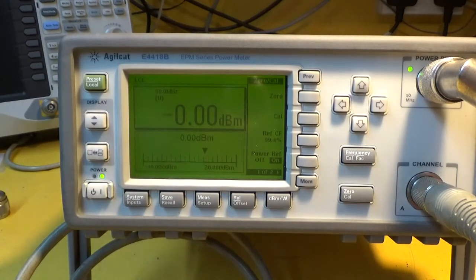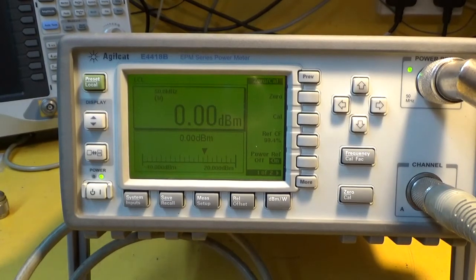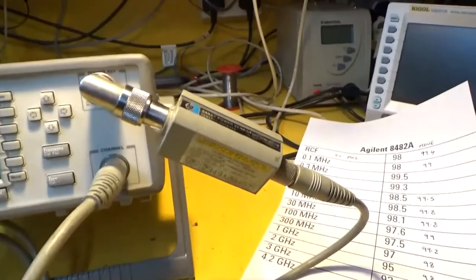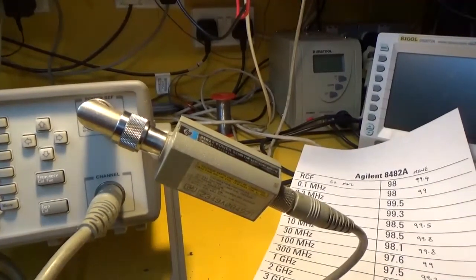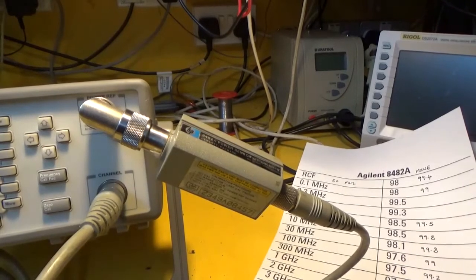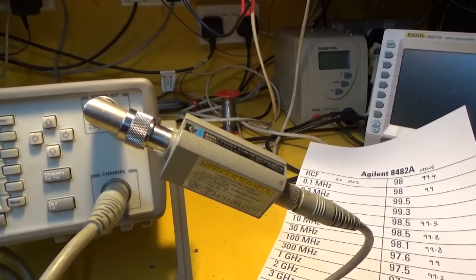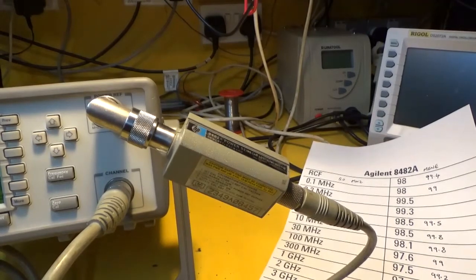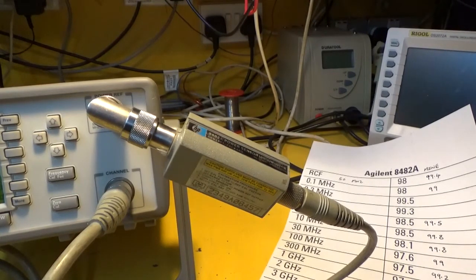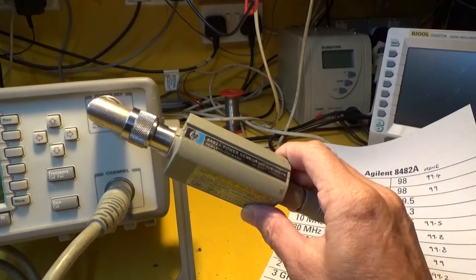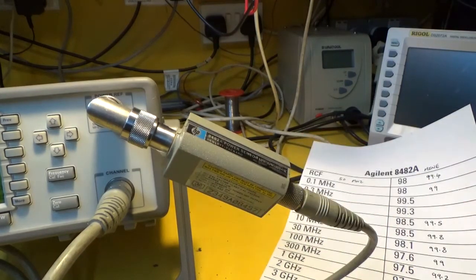So if that's screwed, you're screwed in your measurements. So what should we do now? By the way, this particular sensor uses a thermocouple, or 2 thermocouples, and that's how they measure the power in heat, basically. And when you think about it, this thing's working down to a microwatt, although it does say 0.3 microwatt. Let's call it a microwatt. Imagine measuring a microwatt of heat, and that's what these things do. They measure down to those sort of levels, 1 microwatt of heat.